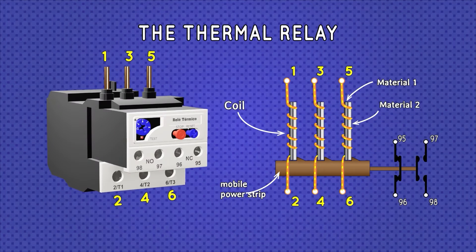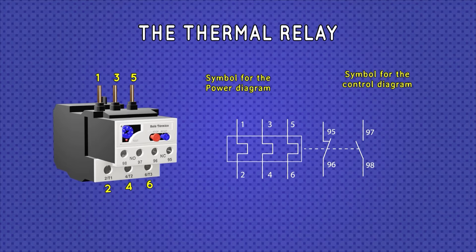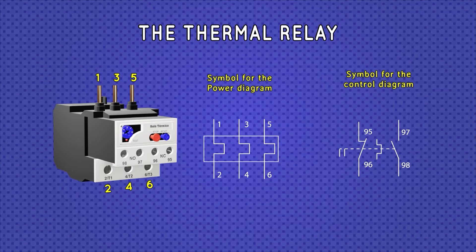As already said, a thermal relay has no breaking power, that is, its main power contacts do not open. Those that change state are only their auxiliary contacts, which are used in the command and control circuit. The symbol that represents this element is the one shown on the screen, which has two parts, one for the power scheme or circuit and another for the command or control scheme. It is also possible to find it separately.